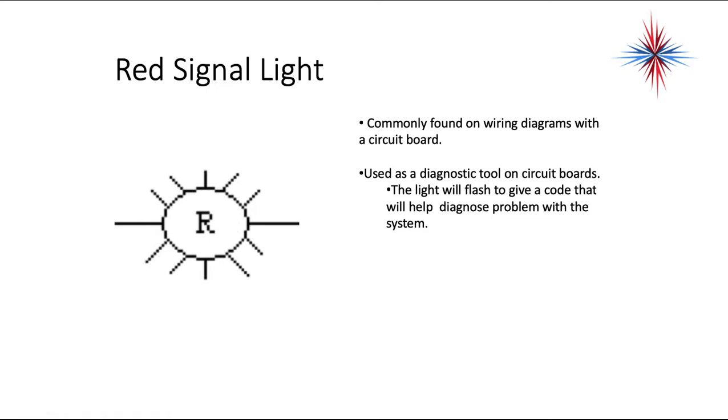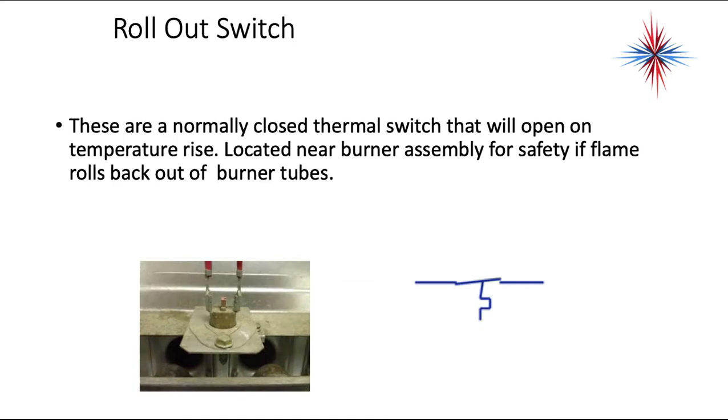A rollout switch is a normally closed thermal switch that will open on temperature rise. It's located near the burner assemblies for safety if the flame comes the wrong direction out of the burner tubes. A rollout switch is a normally closed open on temperature rise thermostat symbol.